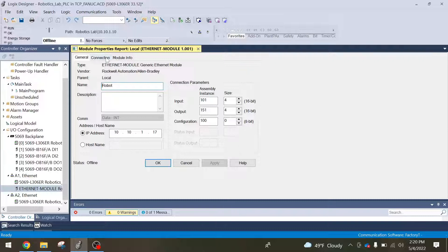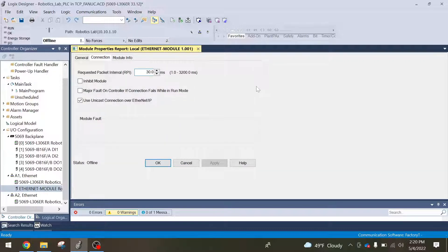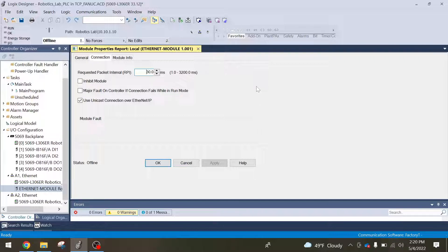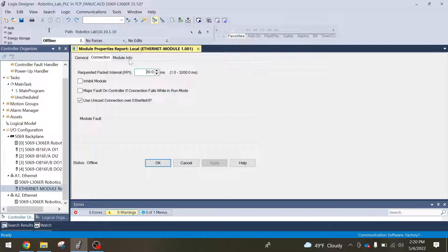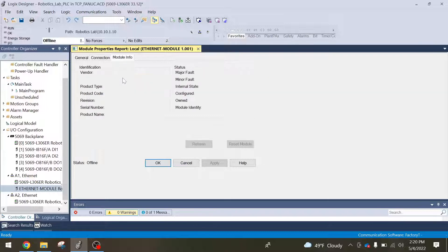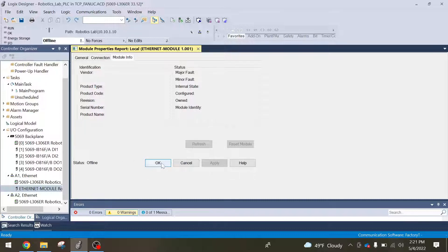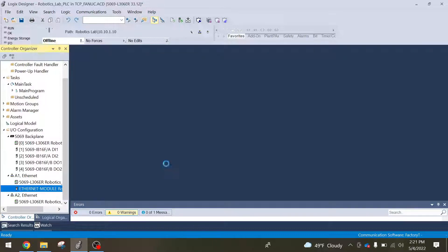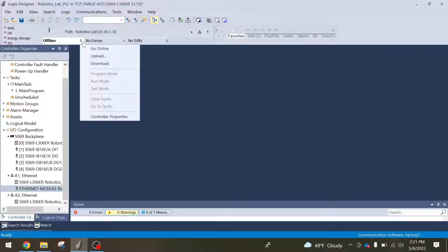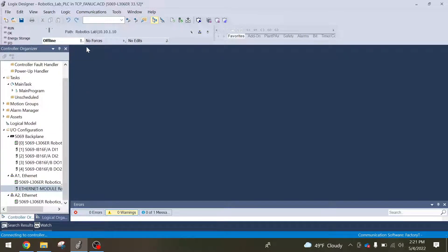Next you're going to go over to connection. The unicast connection, that's totally fine. Then you're going to see your RPI, your requested packet interval. You'll remember from the setup on the FANUC robot side in the adapter config menu, it was auto-populated to 30 milliseconds. This is where that's from. It'll default to 10 milliseconds. I just changed to 30 just because I don't need it to be that fast. Then you see module info. This will auto-populate when you connect to the robot over the network. Now that that's all set up, I hit OK and I can put our controller online to make sure everything connects properly.